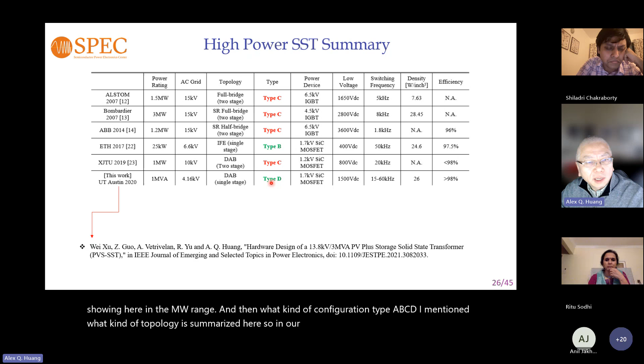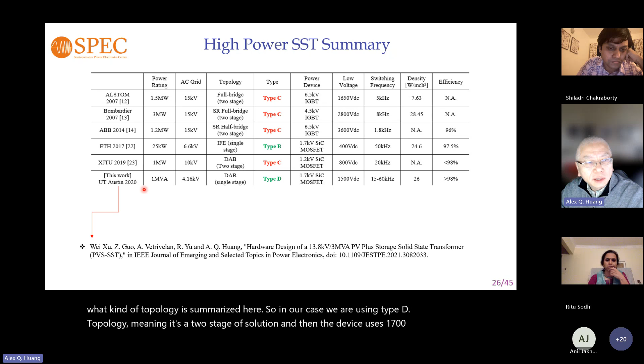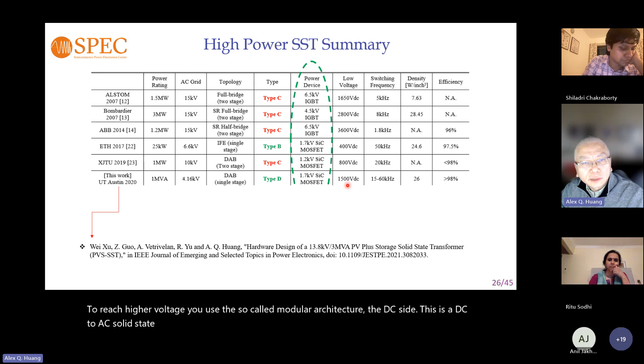The configuration types A, B, C, D I mentioned summarize the topology used. In our case we use type D topology, meaning a two-stage solution, with devices using 1700 volt. To reach higher voltage, you use the so-called modular architecture. The DC side is a DC to AC solid state transformer for a 1500 volt renewable energy system.